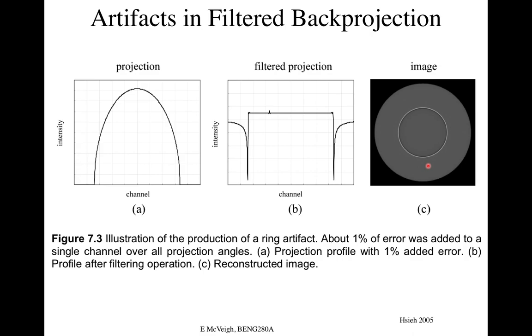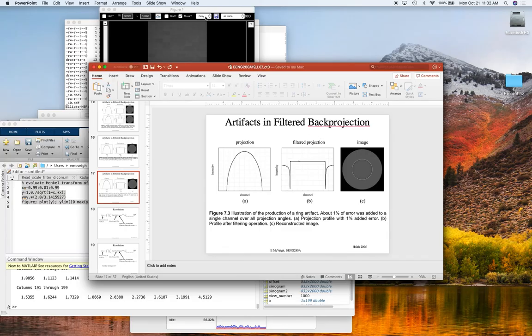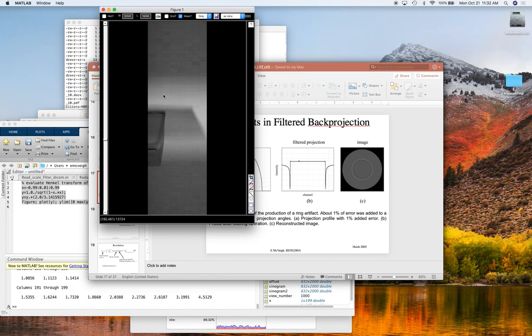Like the first thing they do in the day is they put a phantom in and scan it with a couple of different protocols. And then they'll take an air scan, right? So you can imagine an air scan is a very useful thing in that it gives you the relative amplitudes of those data.